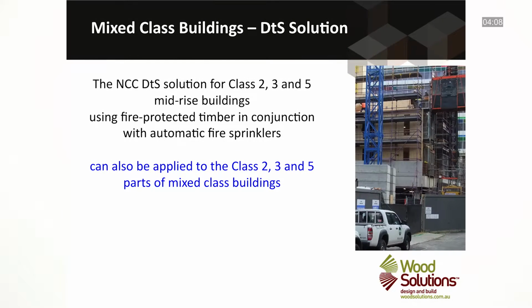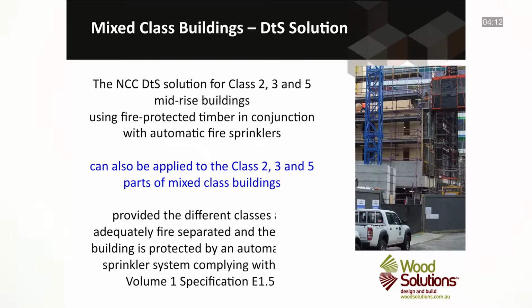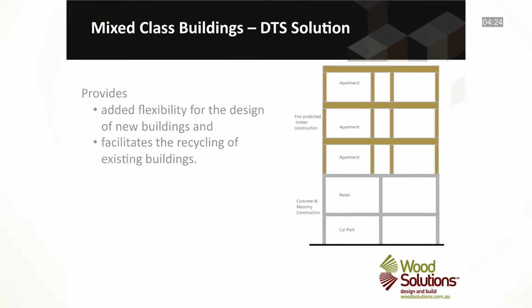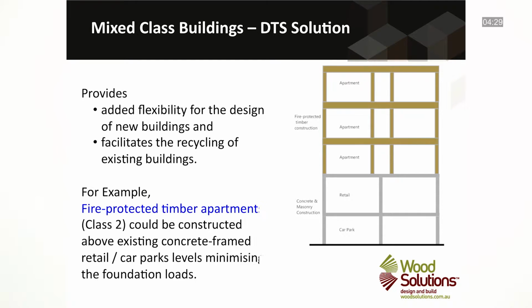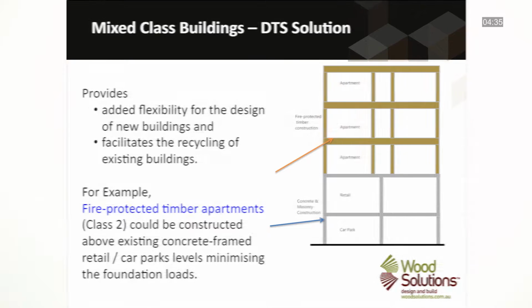This deemed to satisfy solution can also be applied to the Class 2, 3 and 5 parts of a mixed class building, provided the different classes are adequately fire separated and the entire building is protected by an automatic fire sprinkler system. This provides added flexibility for the design of new buildings and facilitating the recycling of existing buildings, as can be seen by the example in this illustration, where fire-protected apartments of Class 2 are being constructed above an existing concrete-framed retail area or car park.